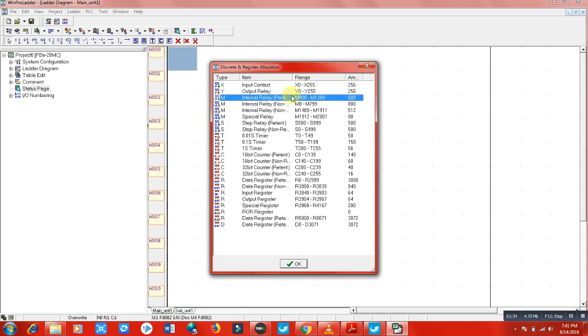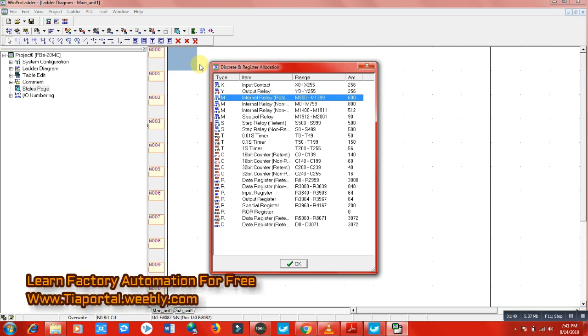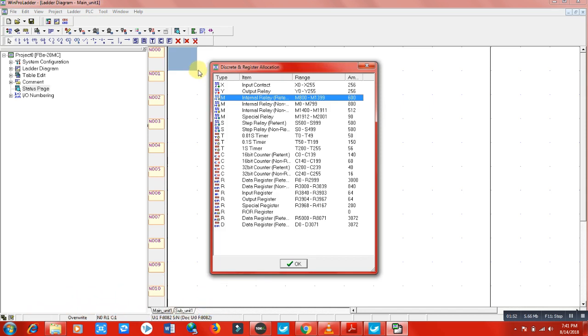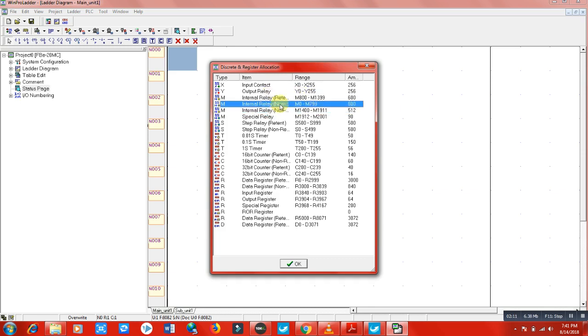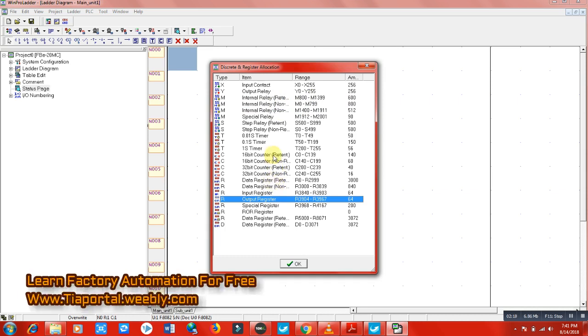What does retentive and non-retentive mean? For example, I'm using a memory whose current value is 6. If my PLC is switched off due to load shedding or another reason, and I switch it back on — if I'm using a retentive memory, it will not lose its value. Retentive means the current value is remembered. Non-retentive means the value is not remembered.